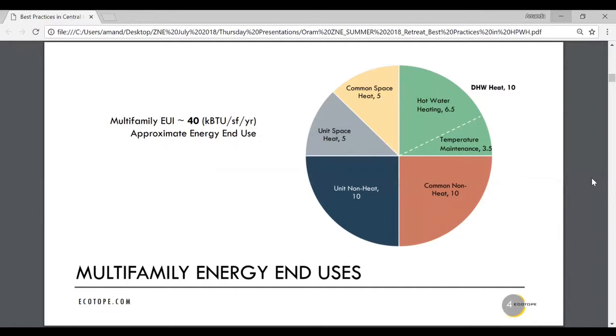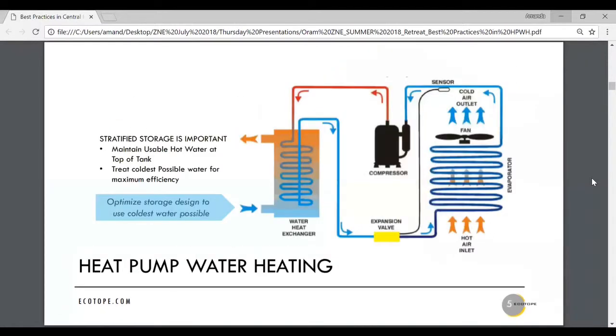It's purely a function of insulation. That is all this is. It's not starting a pump, it's not stopping it - it is purely pipe UA. That's all this is. What is the game as designers? We have to reduce the UA - U value, which would be your insulation times your area. That is the whole function here. And you can't just focus on the plant without also focusing on the distribution. Hopefully today I'll cover the most important pieces of this.